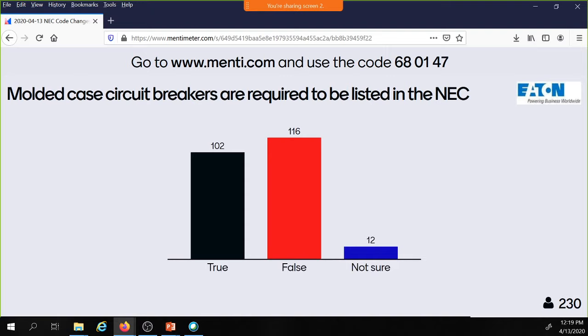And if you put a molded case circuit breaker out and it didn't have a listing mark on it, it would probably send a red flag to the inspector. They would look for a field evaluation, and they would ask a lot of questions. So that listing mark takes a lot off their shoulder. But in the National Electrical Code, there's nothing that says it has to be listed.